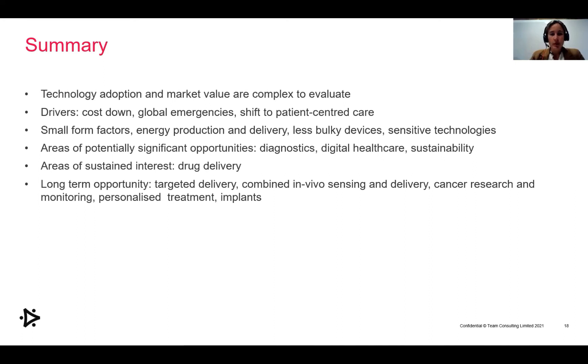An example is bringing molecular techniques based on amplification of DNA, for example, that requires providing heat to catalyze reactions involving these assays. This is a major source of energy and therefore cost in an area where we want to provide more accuracy but keep cost down so that it's more affordable for all countries and more deployable. Challenges are to provide homogeneous distribution of heat — to provide 40 to 60 degrees of heat very rapidly and also to cool down very rapidly — so that tests are short and we use less energy. That can be a huge challenge in the development of these devices.